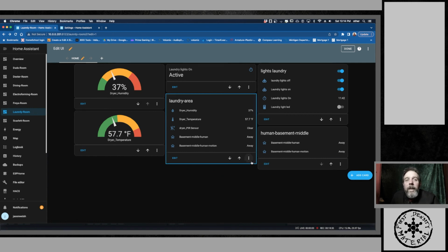But other than that, that is how you set up an area to be lit. As long as you're in that room, it'll stay lit. The timer is kind of a backup unit, so that if that presence sensor doesn't work, at least you have the PIR being activated, and the PIR or the timer is going to be in control for a set amount of time. And then after that, a robot's going to say, hey, well, 13 minutes are up. Is there anybody in here? Okay, let's turn off the lights.